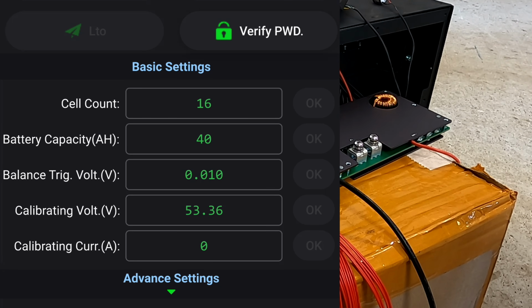Then we have the calibration voltage and current. So if your BMS doesn't show the correct figures, you can use a calibrated multimeter or reference voltage and calibrate the BMS accordingly.